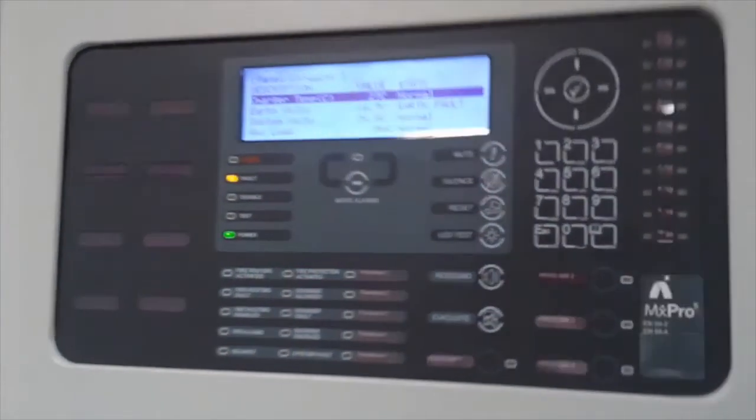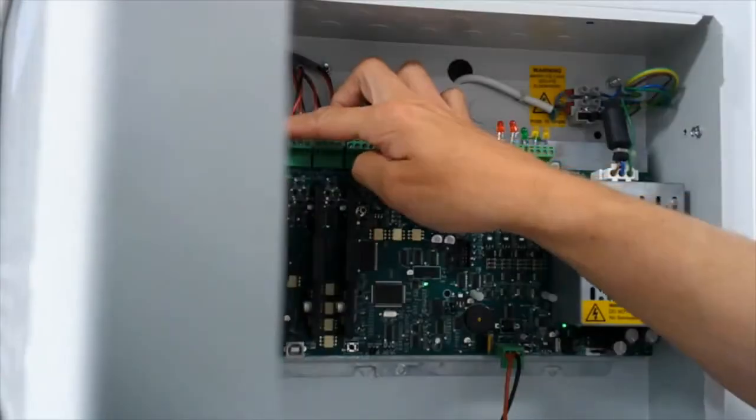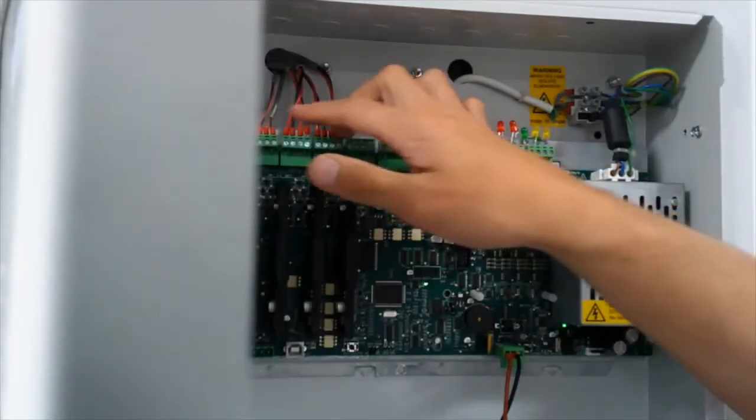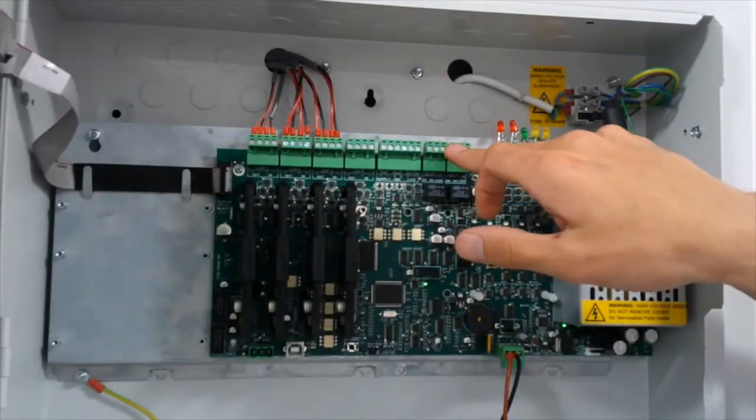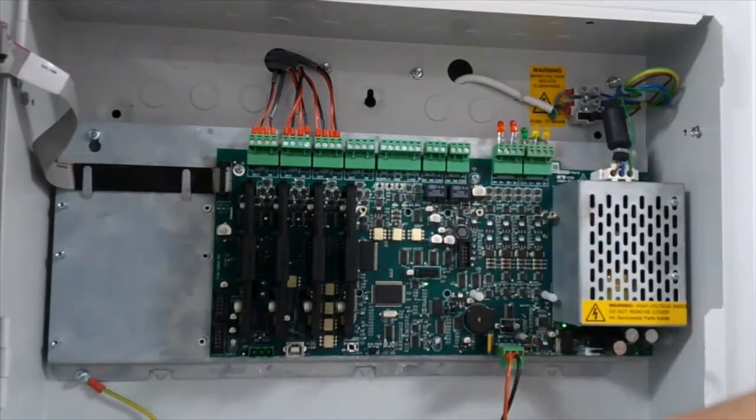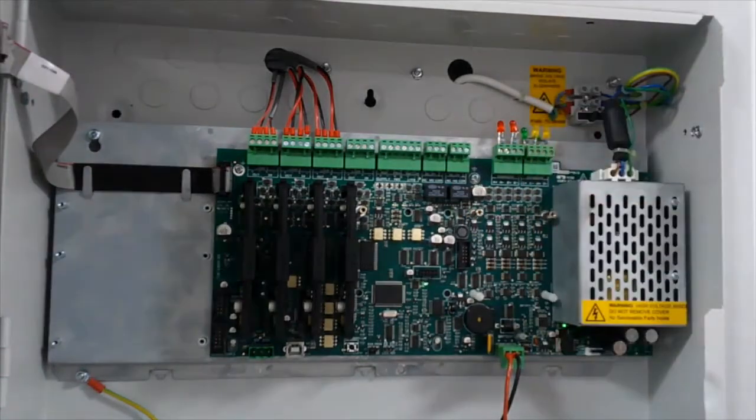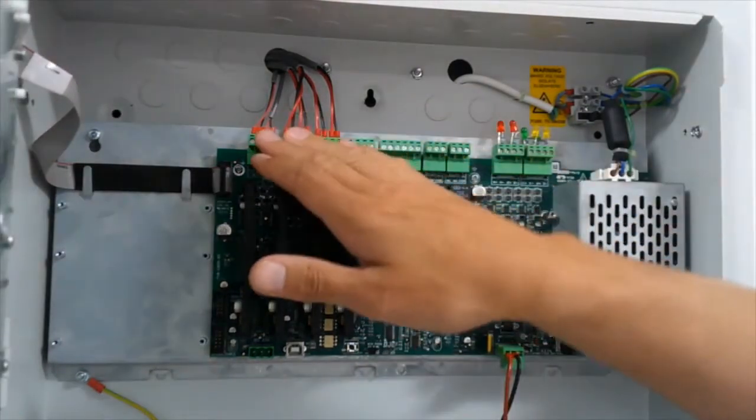So I have identified now, loop 1 is my main culprit. So it's rule of elimination. All the green terminal blocks that we have on the control panel, we can unplug and plug when the system is live, no problem at all. We identify this on loop 1.